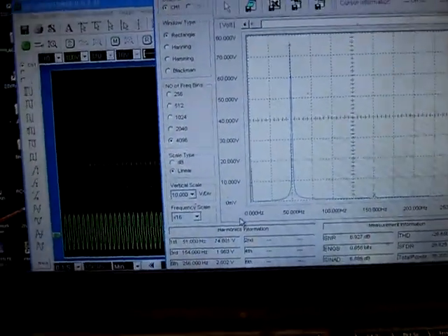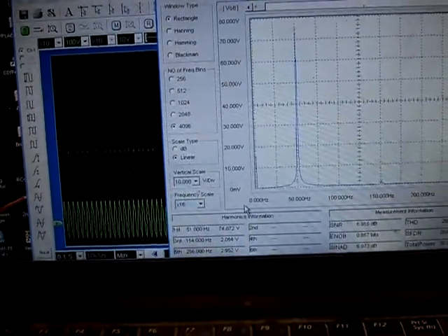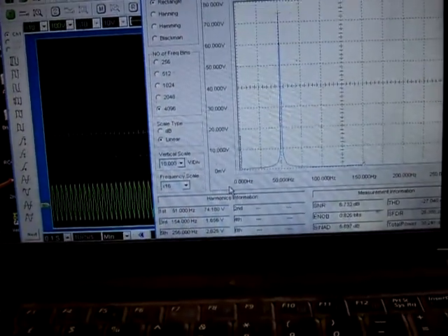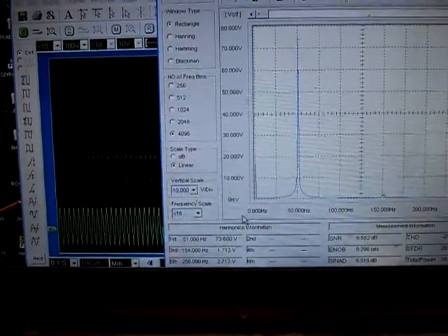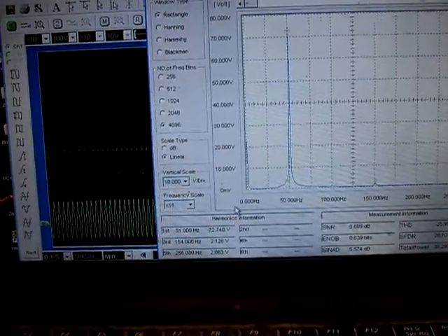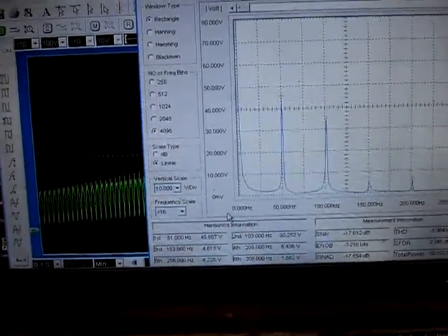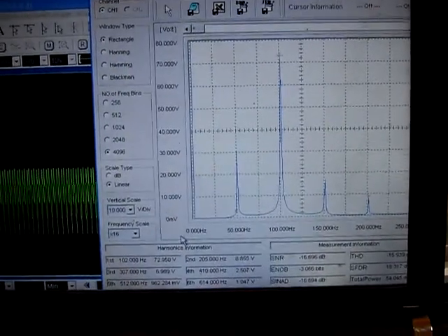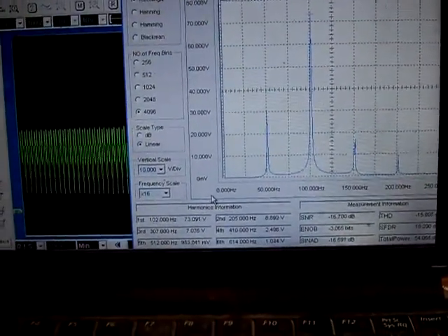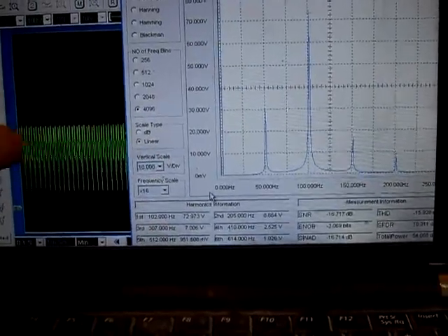Now I'm going to turn the heater up, so I'm just turning the heater up, and you'll see I've got no load on the HT transformer. You see now we're getting a 100 Hz component, which is actually a lot bigger than the 50 Hz component, and you can see there, I'll have to zoom into that in a bit.